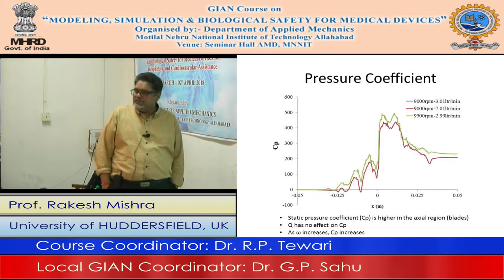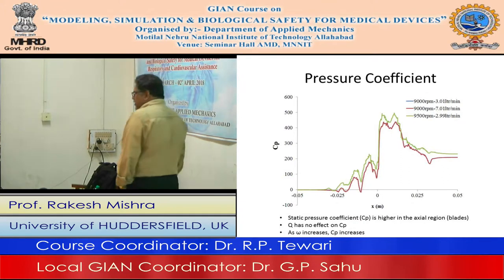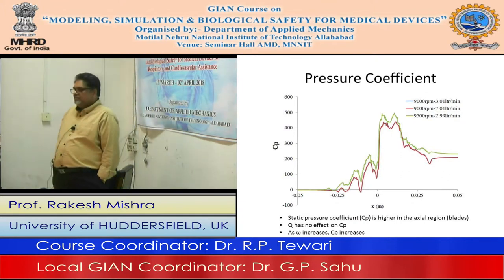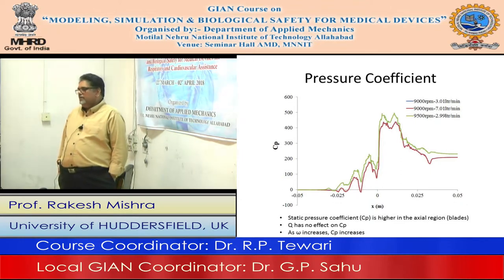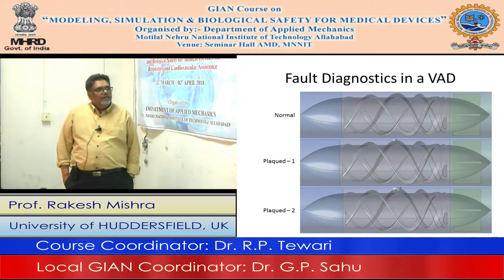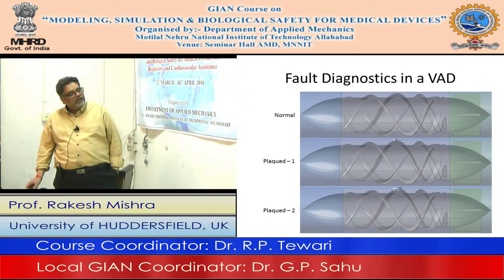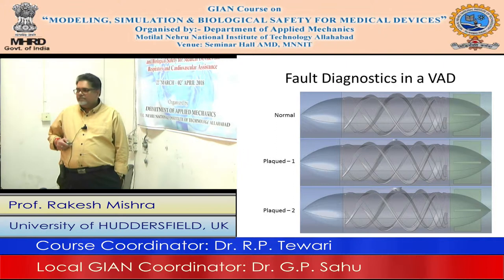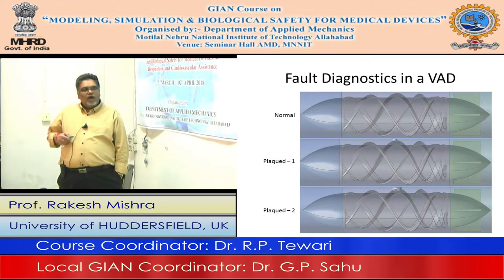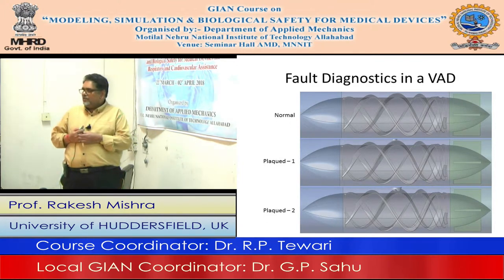Now we start diagnostics in VAD — what happens if a fault appears in the ventricular assist device. Suppose thrombosis has taken place: how will performance be affected, how can we monitor it, and how can we quantify that performance? The top device is the normal one. One device has a small spherical clot formation and another device has a bigger clot formation. I am going to simulate flow at the same conditions and see how the pressure and velocity values change.